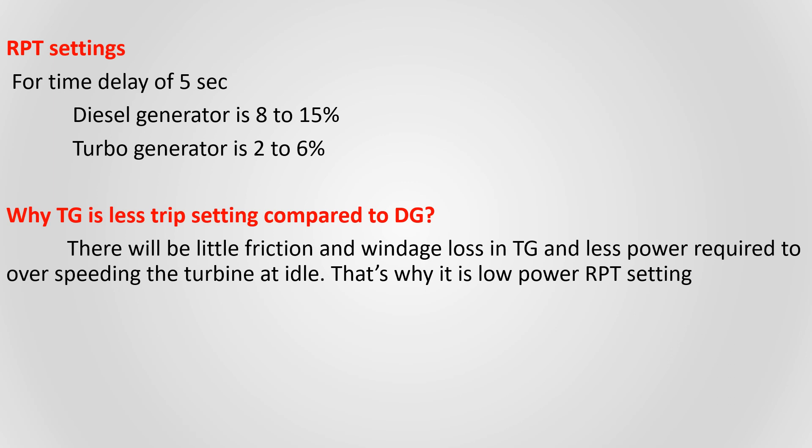A time delay of 5 seconds is used. While paralleling two generators, there will be a power surge and reverse power flow may occur temporarily. So to prevent unwanted reverse power tripping due to power surges, we use a time delay of 5 seconds. The turbo generator has a lower trip setting compared to the diesel generator because the TG has less friction and windage losses, and less power is required to keep the turbine spinning at idle.